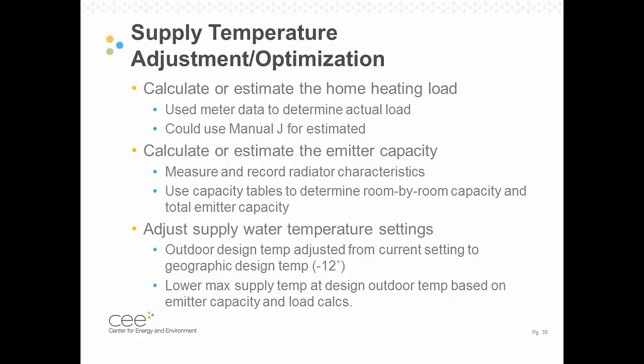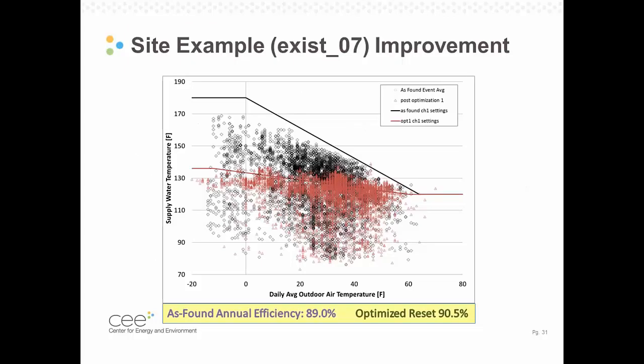So that's the process. It requires you to do a heating load analysis, which can take some time, to do a Manual J or to locate the utility bills and do that analysis. You also have to do this room by room capacity walk around, measure all the emitters, look up some lookup tables, and do those manual calculations. So this isn't a 5-minute process, but it's also not a half a day process. But it does take some time.